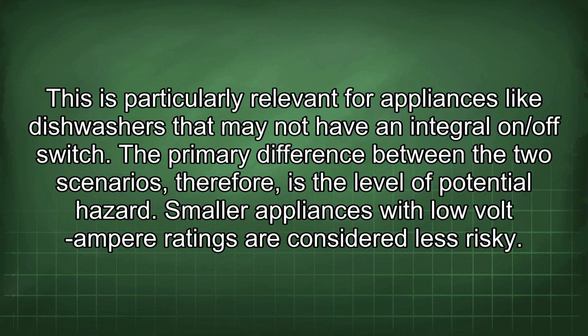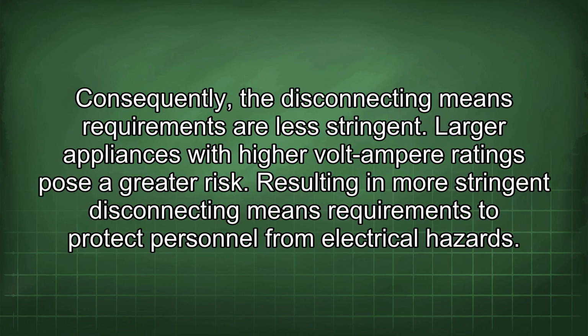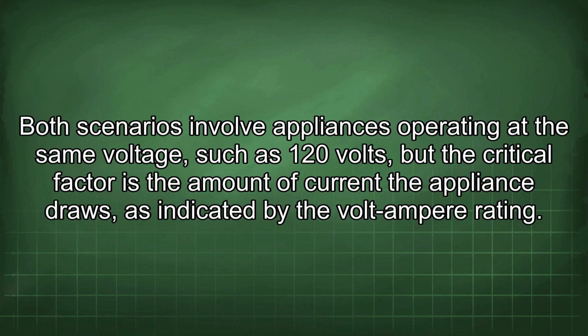Smaller appliances with low volt-ampere ratings are considered less risky. Consequently, the disconnecting means requirements are less stringent. Larger appliances with higher volt-ampere ratings pose a greater risk, resulting in more stringent disconnecting means requirements to protect personnel from electrical hazards. Both scenarios involve appliances operating at the same voltage, such as 120 volts, but the critical factor is the amount of current the appliance draws, as indicated by the volt-ampere rating.